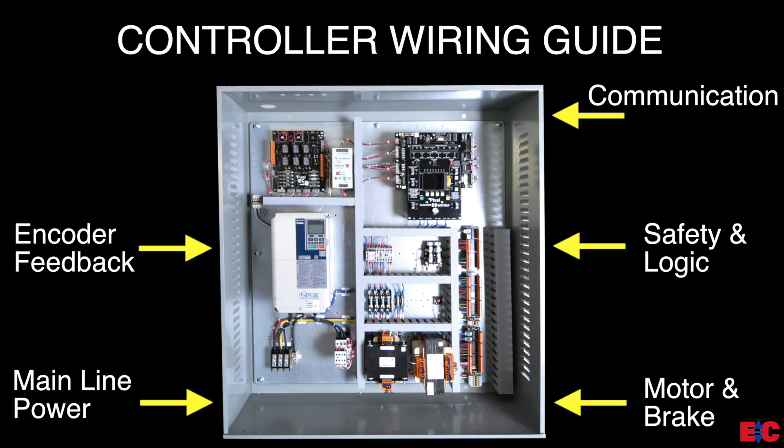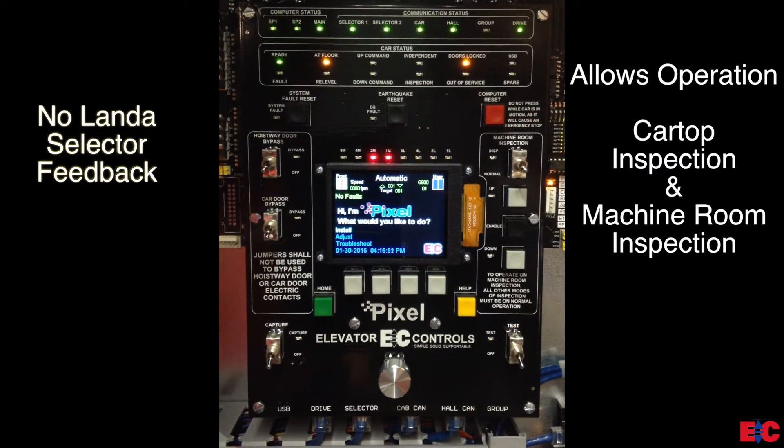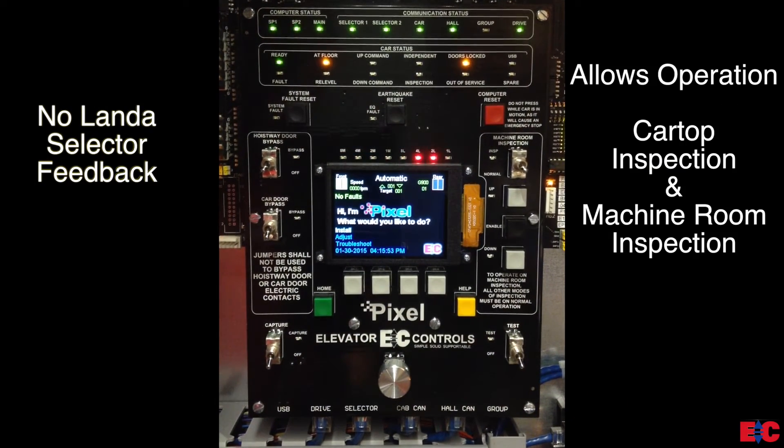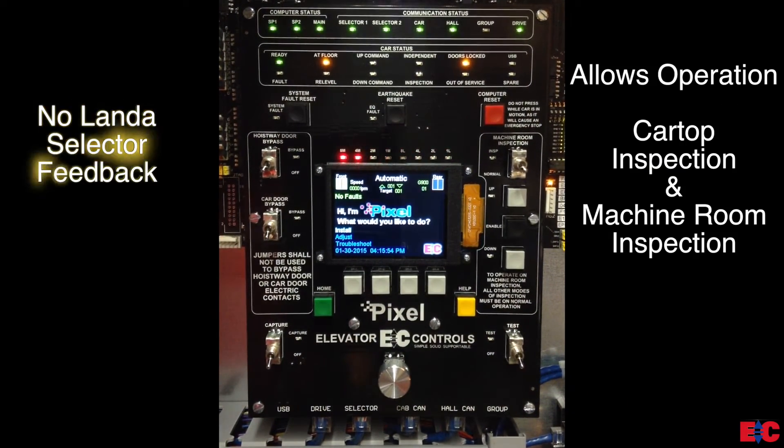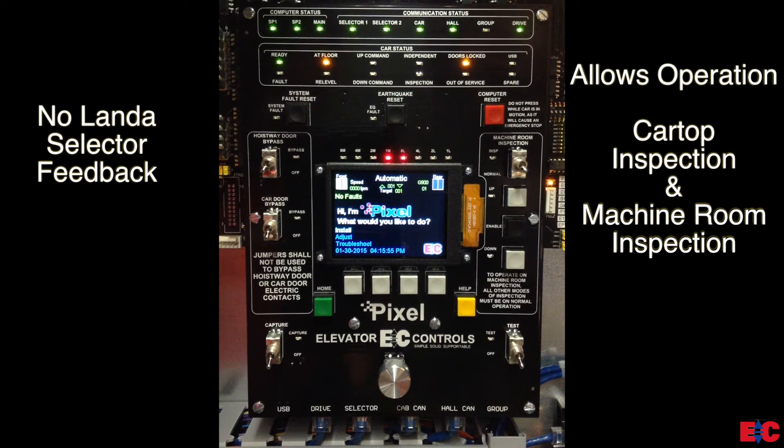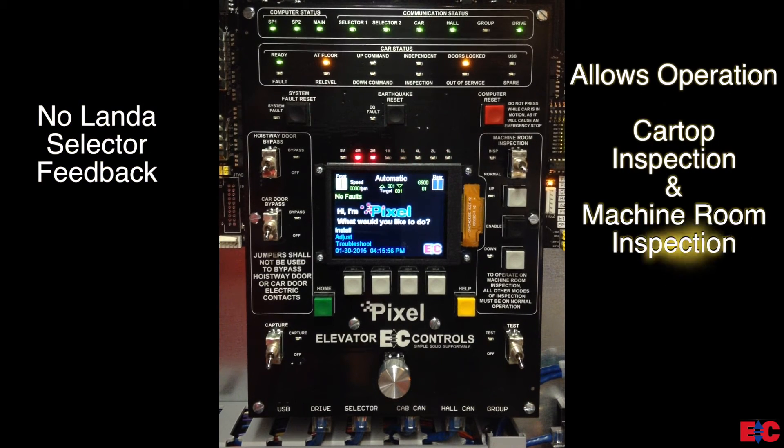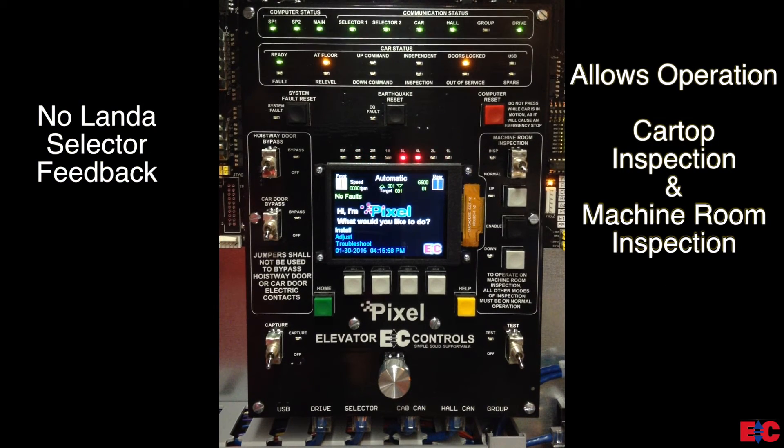Keeping all this in mind, let's now go to the pixel main processor board, PMP, to go over how to enable construction mode. In construction mode, the pixel does not require the Landa Selector Feedback and can be operated in either car top or machine room inspection mode.